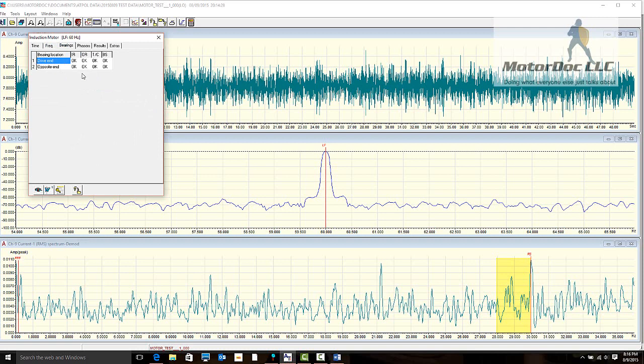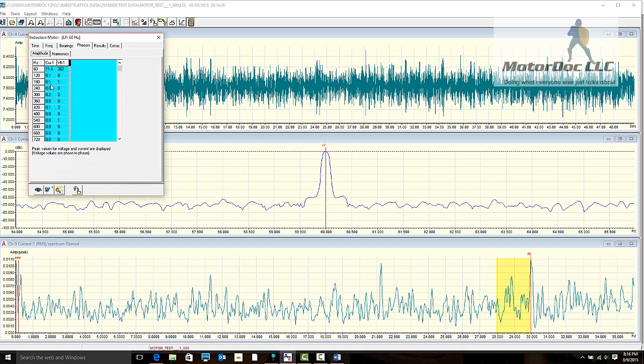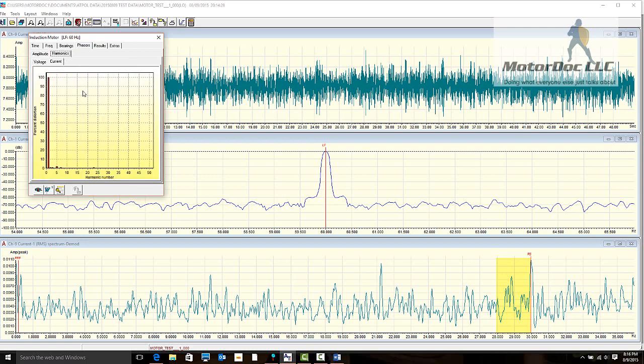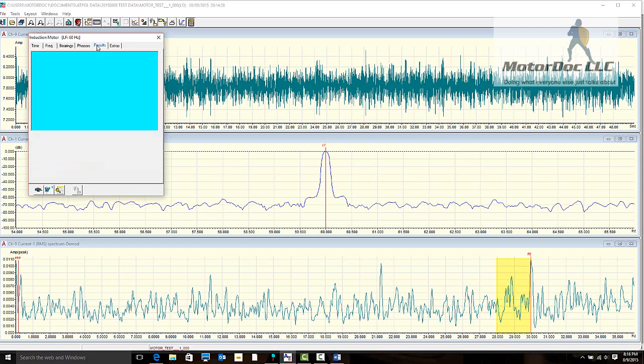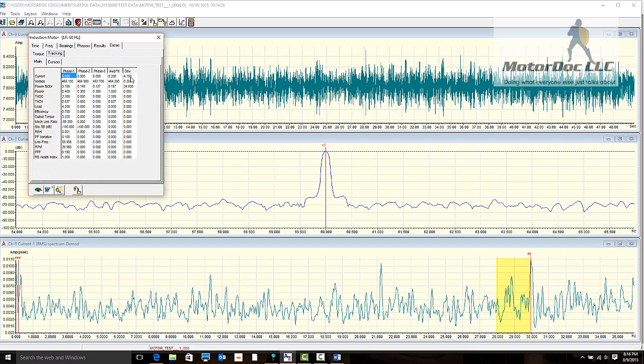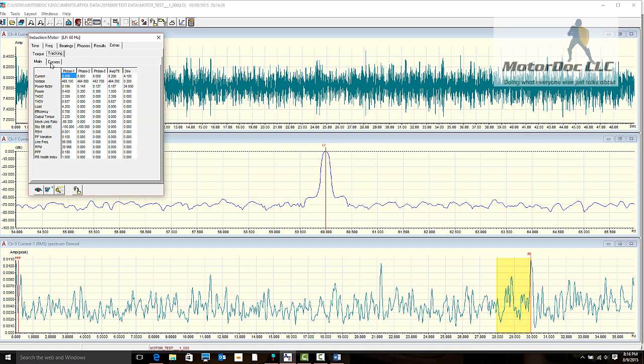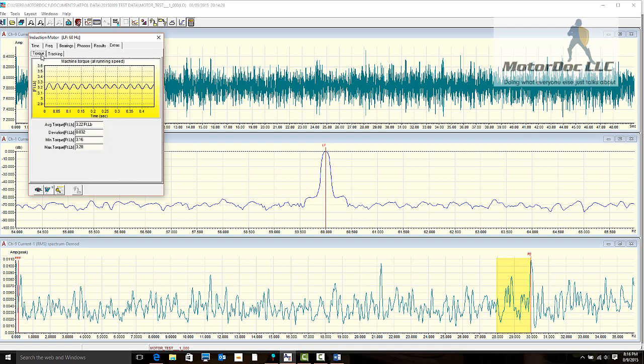The next thing I can do is take a look at my line frequency. What it's calculated is my running speed, pole pass frequency, and my harmonic distortion in current and voltage. Bearings shows everything's okay. Phasors, this would be my power quality for harmonics. As well as I can take a look at the amplitude here. Graphs are far better. Results, this is what it has detected automatically. And then extras include all the information that we're looking at, including the rotor bar health and so on.